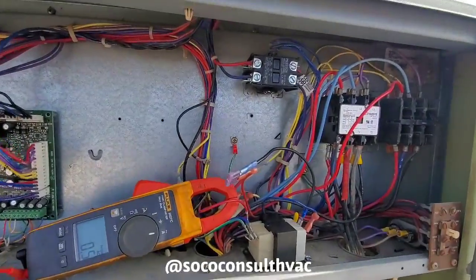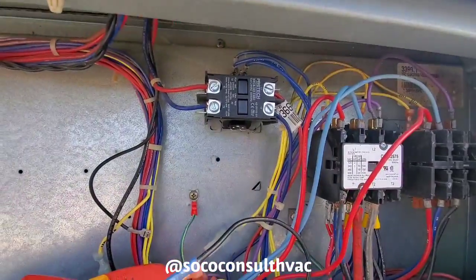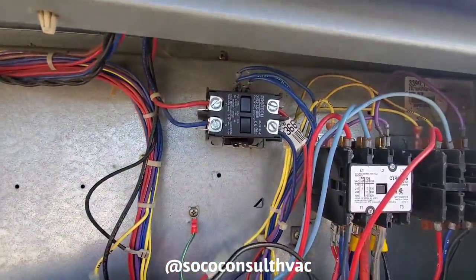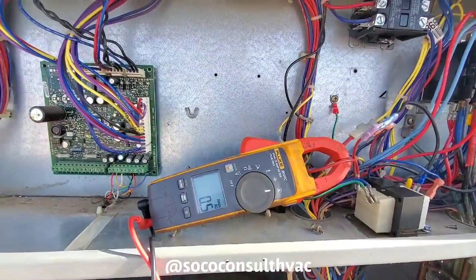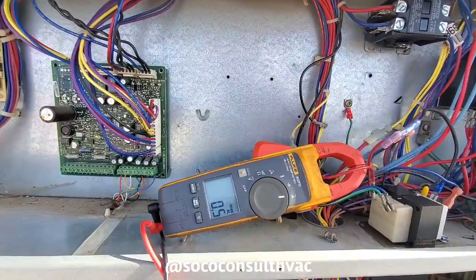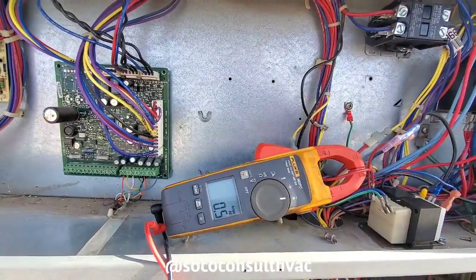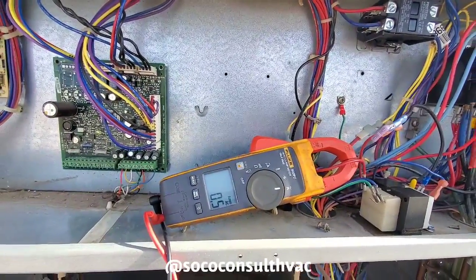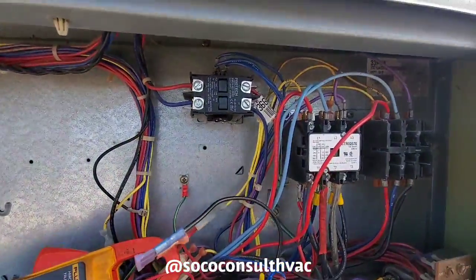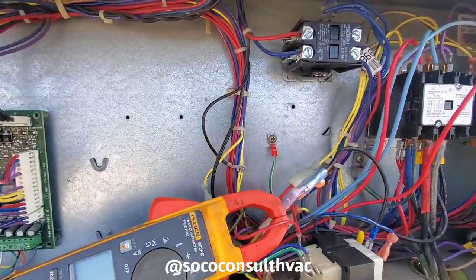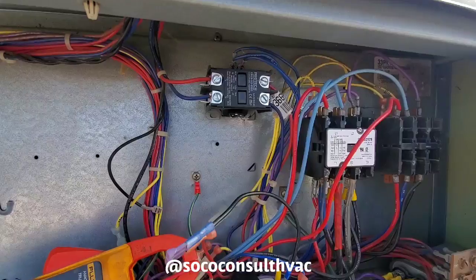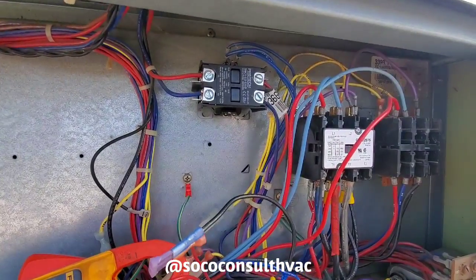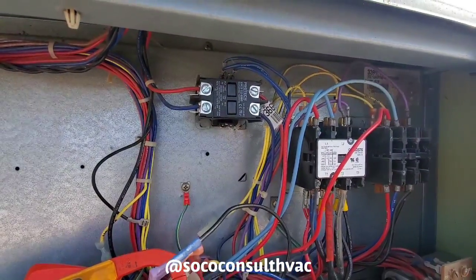Okay, so I've powered the unit up after removing the coil wire from that fan contactor, and we've been powered up for about a minute, and this is what we're getting: 0.5 amps, which is pretty normal for control voltage. Of course, nothing's running yet, but I never got this far until I pulled that wire. So that contactor, I suspect, is shorted to ground, and we're going to verify that with an ohm meter next.